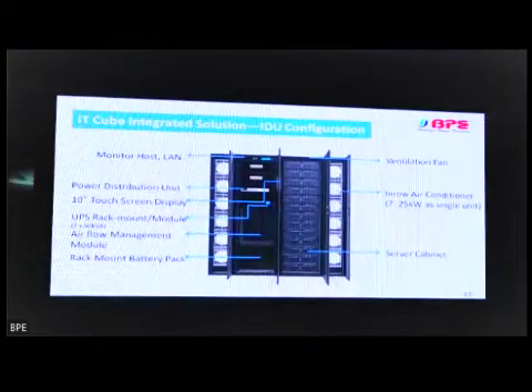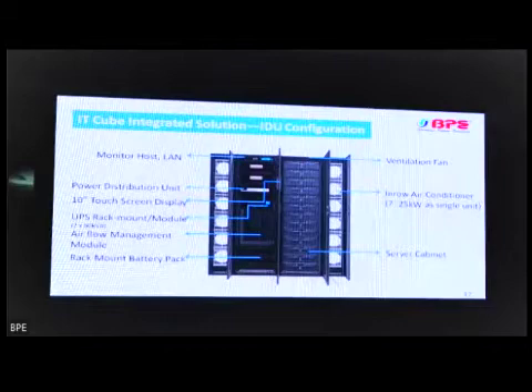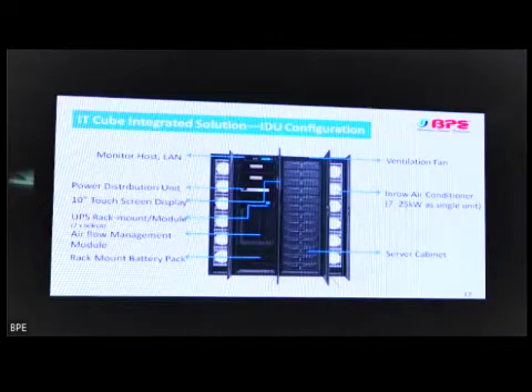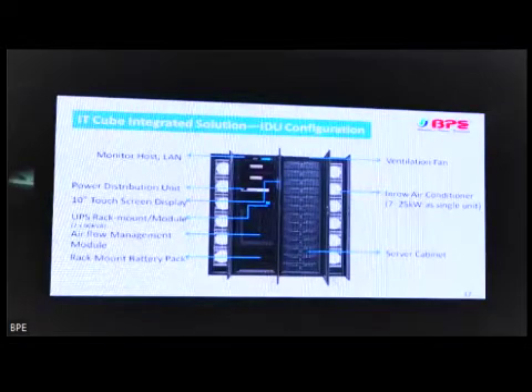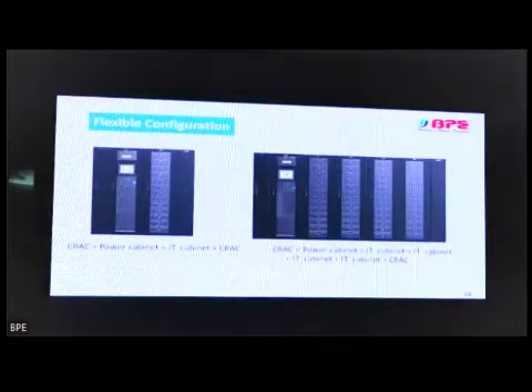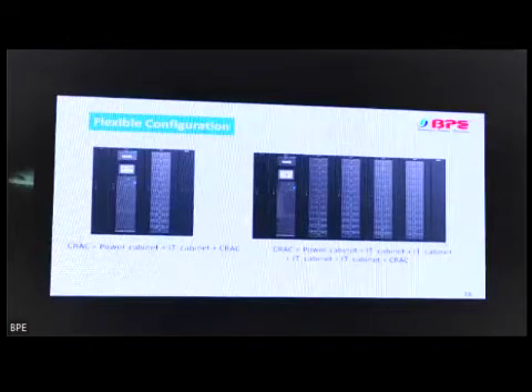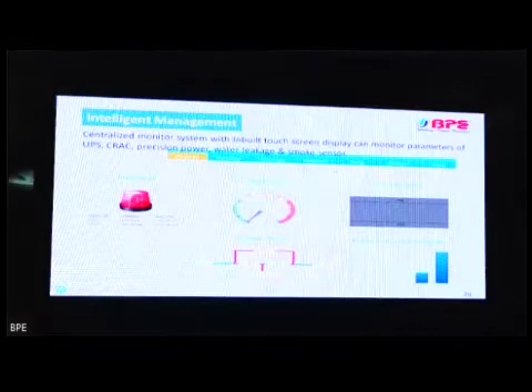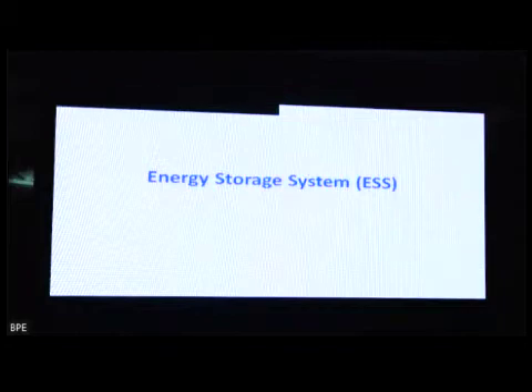Here is the smart cabinet, where the space for server is 30U. This is another one, bigger one, with the inbuilt air con from 7 to 25 kilowatts. And there is a provision of CRAC unit along with the server racks. This is the bigger one. Flexible configuration is there: CRAC unit plus power cabinet plus IT cabinets and plus CRAC again. This is the monitoring which we will see on the screen. The alarm information, the UPS load, cold aisle temperature, also the power consumption.